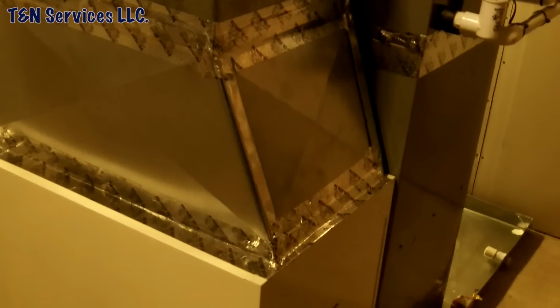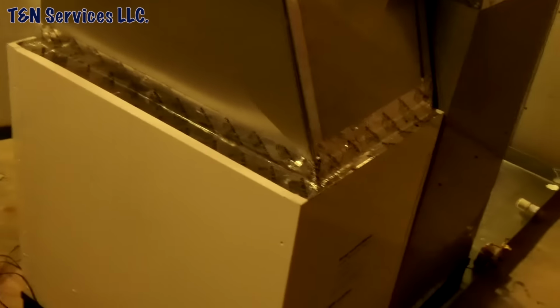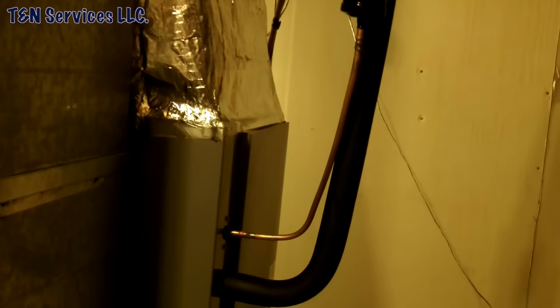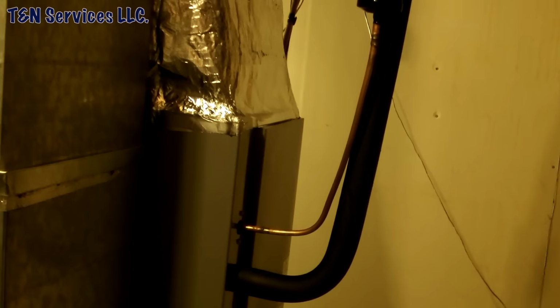And put the door back on it. Alright, door's back on. Now the reason I chose to do the 90 filter box is simply because I didn't want to have to replace all the ductwork coming straight down. I didn't want to offset it out because then we would have been into the room. And when I came the other day, this room was full of stuff, so doing the 90-degree was just a better option. On top of the coil, you can see I did a transition, and it goes up at an angle like that, because the old furnace used to come just straight down.